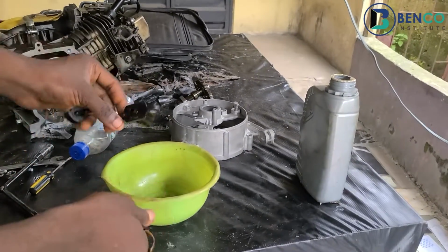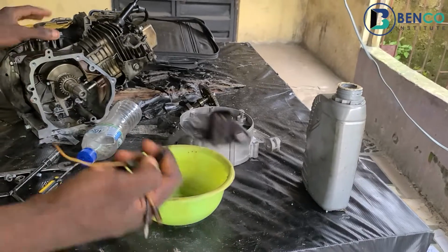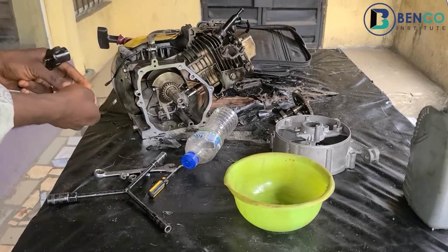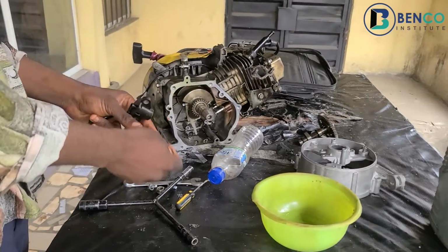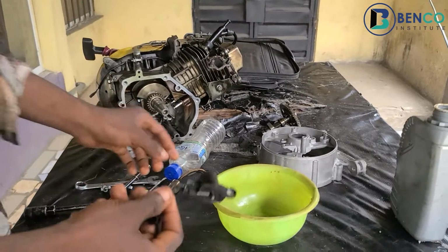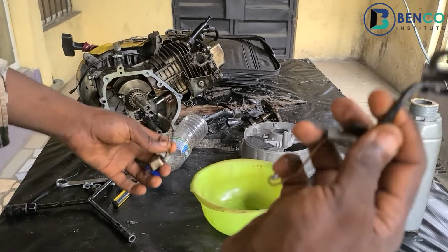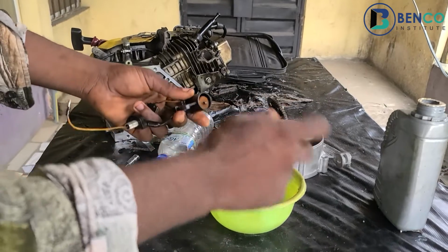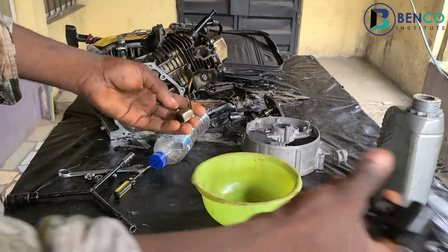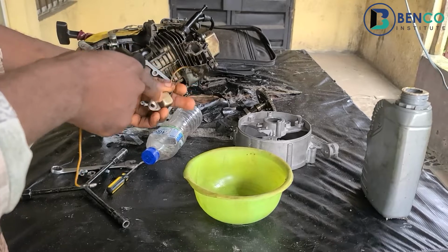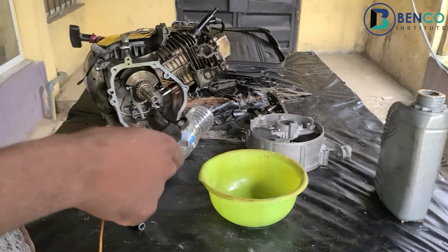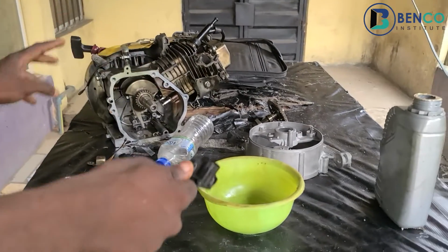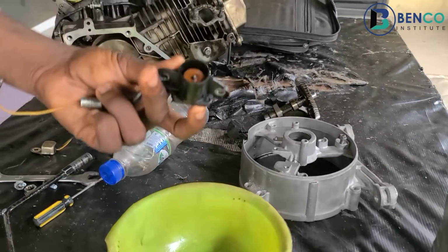Okay, guys, we've loosed them out. We took out this oil sensor from inside of the crankcase, and then we took out the oil switch attached to the crankcase. Remember, I said the function of this particular oil sensor is to sense that the oil level has gone down, and after sensing it, it sends the signal down to this oil switch, which eventually sends it to the electrical component of the generator that automatically shuts the generator when oil is down. But this is how this functions.